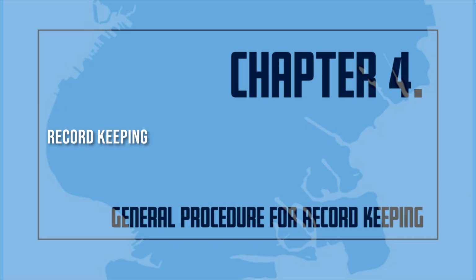Riser Card. In addition to those records required by the National Fire Protection Association 25, as mentioned above, an approved card bearing the dates of each inspection, the Certificate of Fitness number, and signature of the Certificate of Fitness holder shall be posted on the premises near the main water supply control valve. This approved card shall not replace or supersede the detailed record of inspection.